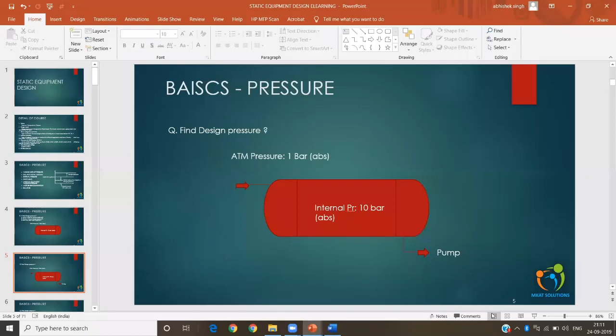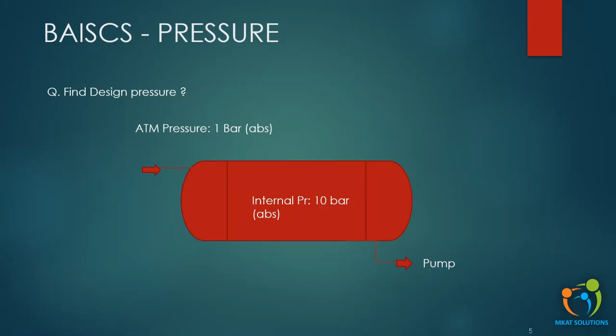Understood? So actually external pressure will act only in the failure condition. But if we envisage that this condition may happen, then we need to design this vessel for external pressure also. Please remember that it will not happen in operating condition. In operating condition, internal pressure is always high. It will only happen in failure condition. So if we expect that there will be some conditions like that, then we need to design the vessel for external pressure also.